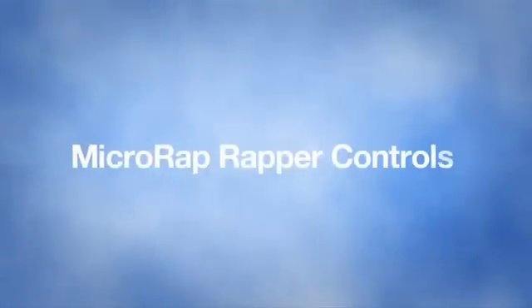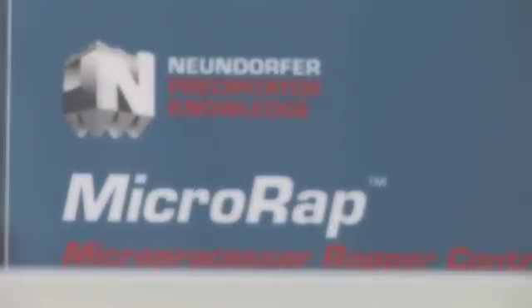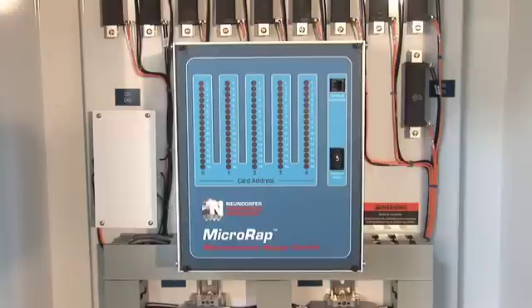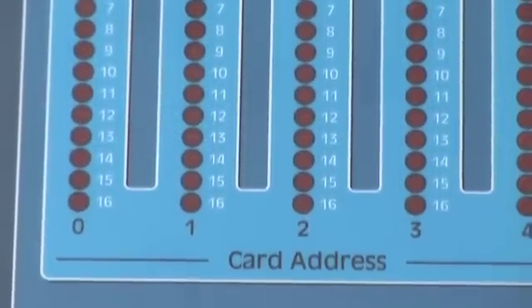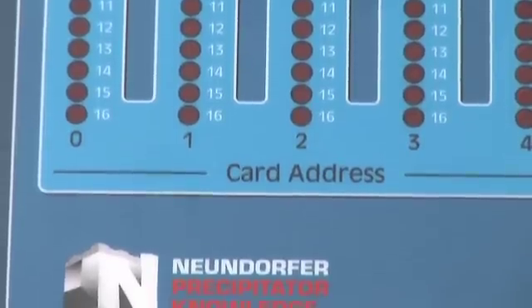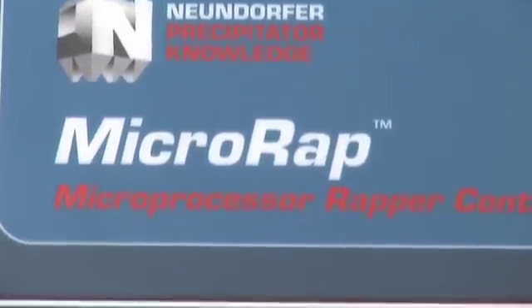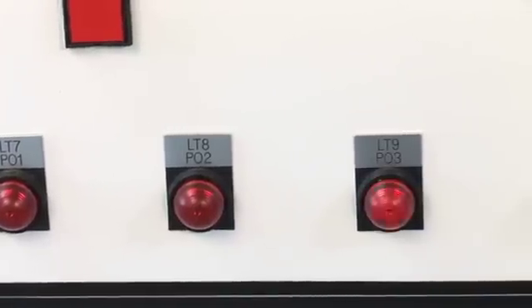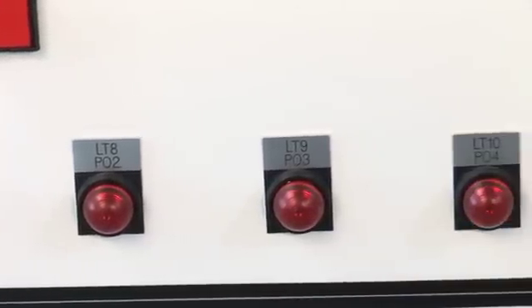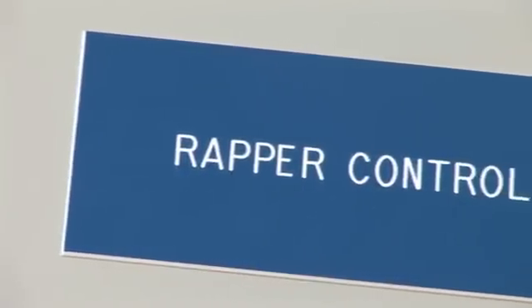The next element of the Neundorfer hands-on learning program includes the MicroRap rapper control simulator, teaching users how to read the display board of the MicroRap. The user can observe the board signaling when the rapper fires, when it actuates, and when it doesn't actuate. The user can see problems and work toward possible solutions. The rapper control simulates a short, an open, and allows users to connect an actual rapper to make sure it's firing properly.